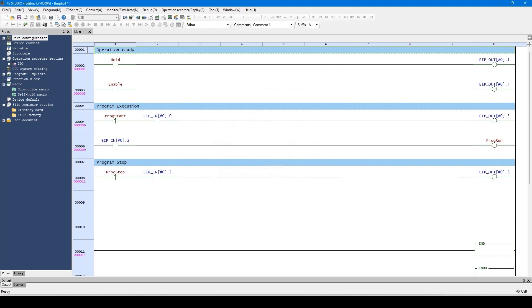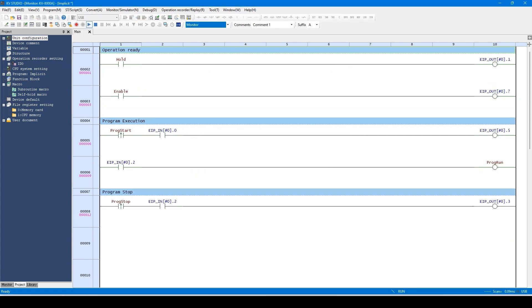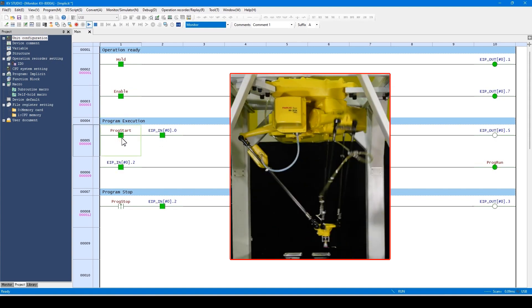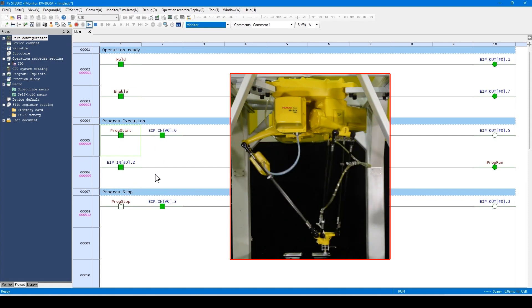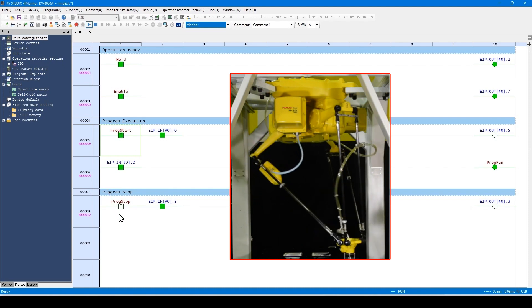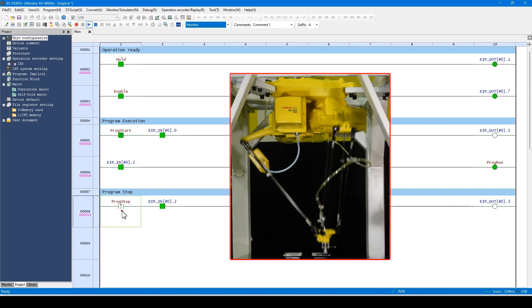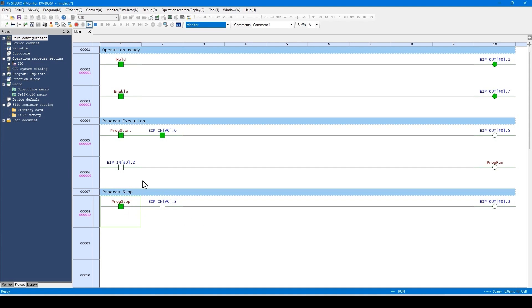I'll transfer the program to the PLC to check the performance. Transfer completed. First, I will turn on the hold and enable signals. The robot should go into standby condition and the command enable signal will turn on. Let's turn on the first two signals. As you can see, the robot goes into standby condition and the command enable signal turns on. Now the robot program should be executable. Let's turn on this variable to execute the robot program. The robot program started and the PROGRUN signal turned on. Next, I can stop the robot program by turning on the cycle stop signal. As you can see, the PROGRUN signal turned off and the robot program stopped.